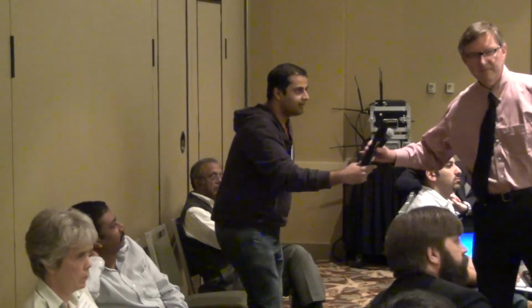All right. So first, 90-5 is a technical report. And as a technical report, what it defines are the changes that need to be made to 61850 to implement R-Goose and to implement R-SV. So Goose, going forward, will have an additional profile. And the additional profile will be the addition of the IP and UDP header. Will it affect timing? Yes, there's a slight delay that's added on by adding in the IP header, because now going through a network, the message has to be routed.